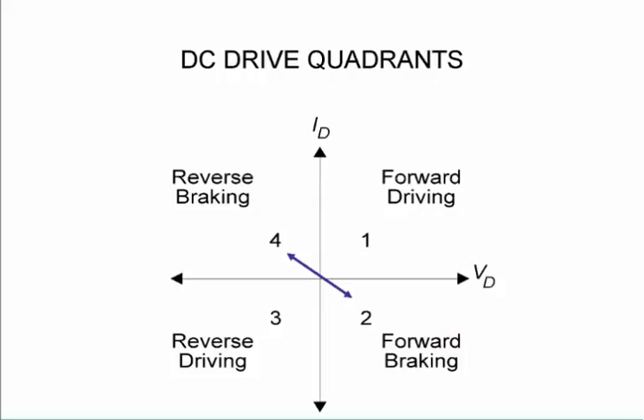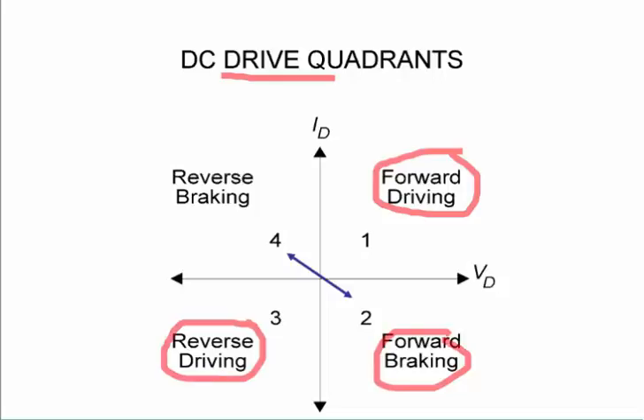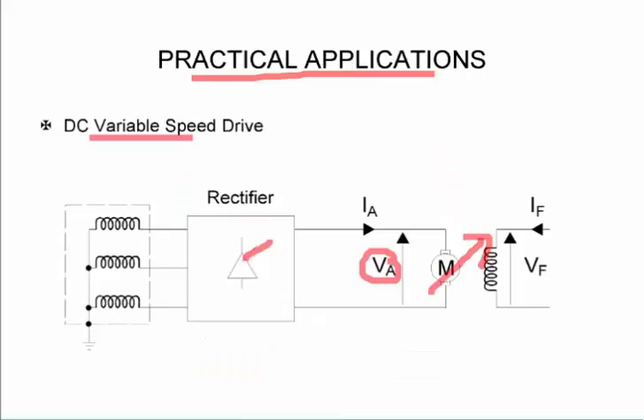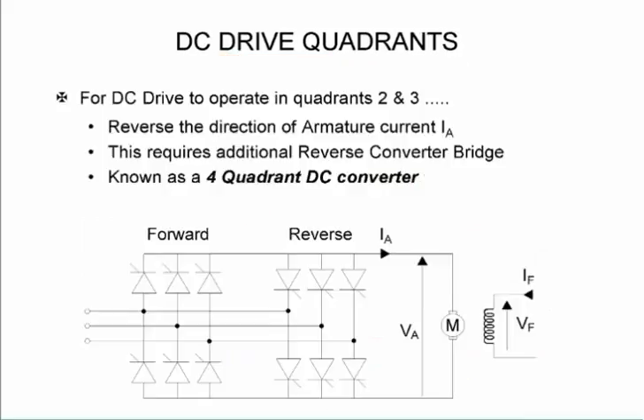Now my DC drive can operate in different quadrants. It can be forward driving, or it can be forward braking, or it can be reverse driving in the opposite direction and reverse braking. But with what we have over here it's not possible to operate in all the quadrants. If I want to operate in all four quadrants I need a four quadrant DC converter.